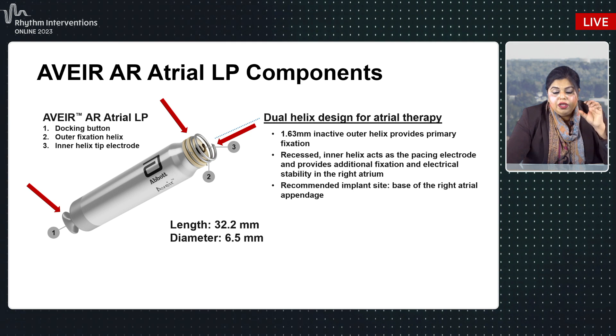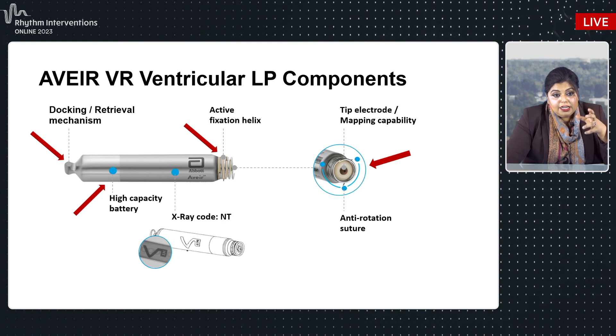It also has an electrically inactive active fixation helix, which is used to implant the device. But the mapping is using a tip electrode. The cathode sits at the dome of that helix and allows for that pre-mapping capability that you'll see during the case. The helix also has these anti-rotation sutures or nose cone sutures that prevent counter-rotation of the device. You'll see the battery, which is a newer battery than its predecessor, the NanoStim, and you'll see some of the battery longevity. It also has a docking button, which is for delivery as well as retrieval.